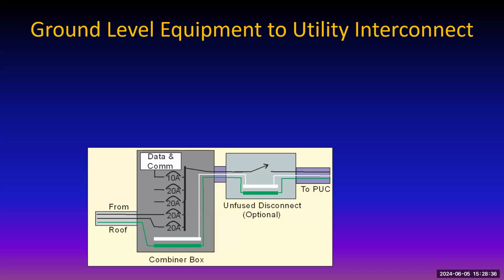There may or may not be an unfused disconnect, depends on the size of the system. If it's over 10,000 or over about 12,000 watts DC rating, or over 10,000 watts AC rating, then you need an external, easily accessible unfused disconnect that the utility has access to. Otherwise, the disconnect has to be accessible, according to that definition.